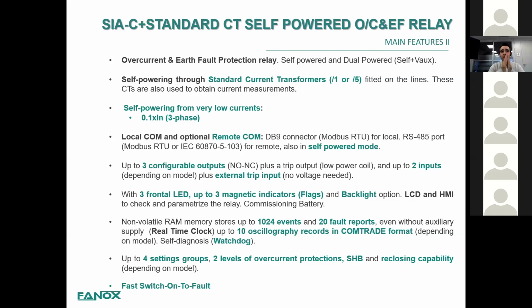As I told you before, we also have local communication. In this case, it's a DB9 connector, also working with Modbus RTU protocol, and remote communication is also available in self-power mode through our RS-485 port. In this case, we have Modbus or IEC 103 protocol. We have 3 configurable outputs and up to 2 inputs, an external input, and the trip output for the low power coil. We have more indicators on the front of the relay: 3 frontal LEDs, up to 3 magnetic indicators, and also a backlight option for the LCD, which can be very useful depending on the situation and the placement of these relays. Also, it's possible to commission with a battery, and of course, there is an LCD and HMI to check and parameterize the relay.